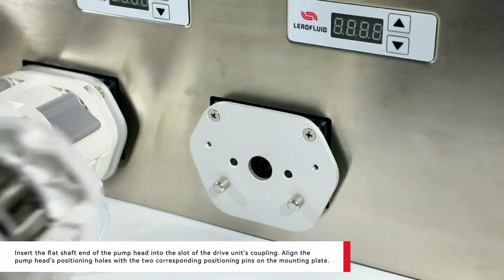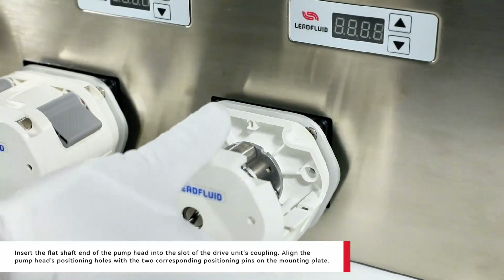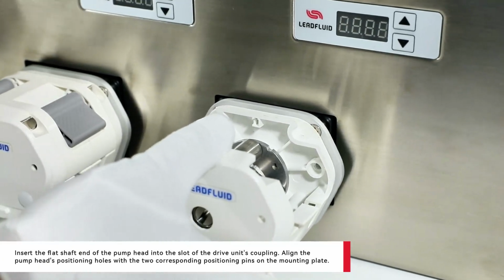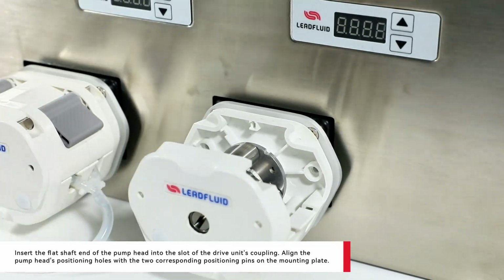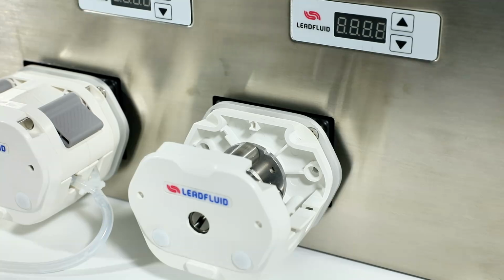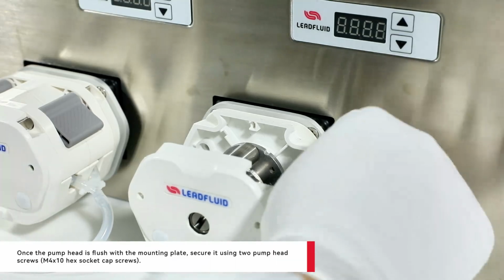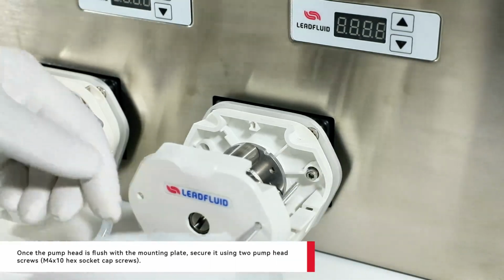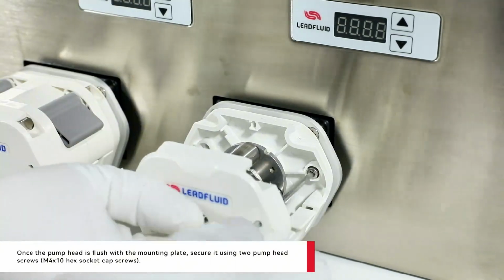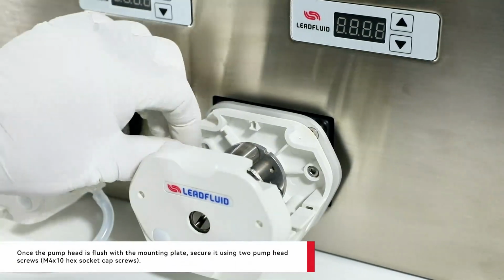Insert the flat shaft end of the pump head into the slot of the drive unit's coupling. Align the pump head's positioning holes with the two corresponding positioning pins on the mounting plate. Once the pump head is flush with the mounting plate, secure it using two pump head screws, M4X10 hex socket cap screws.